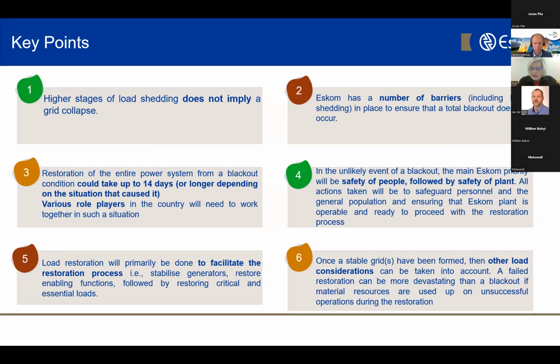So restoration, as I have mentioned, is between 6 and 14 days. It could even be longer depending on the status of the network at the time of the event. The restoration will primarily be done to facilitate the restoration process. What do I mean by this? The loads that we pick up in the different stages of restoration will firstly depend on what is available on the network for us to bring back. It would typically be resistive load, stable load, such as domestic load first. We do utilize some of our industrial customers for this.